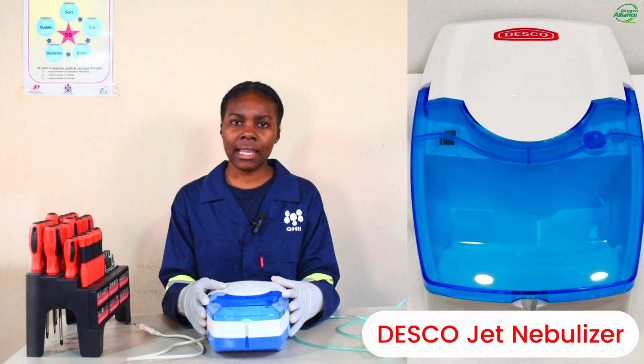In this video, we'll be working with a Desco jet nebulizer. Like other jet nebulizers, this nebulizer uses pressurized air to convert the liquid medication into a fine mist. It has a power rating of 130 watts and it operates on 220 volts AC at a frequency of 50 Hz. This jet nebulizer assembly consists of a nebulizer kit and a compressor unit. This nebulizer's compressor draws in ambient air and compresses it to a pressure of 9 to 19 psi.